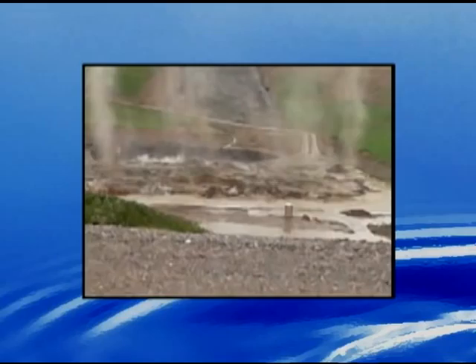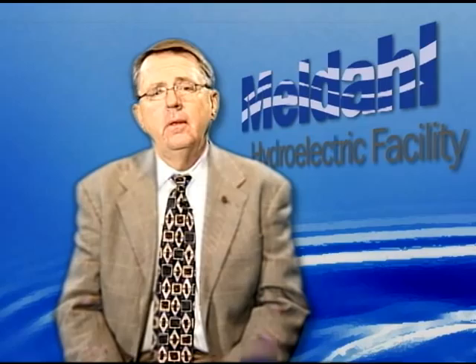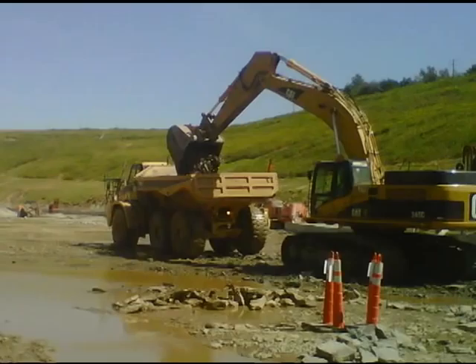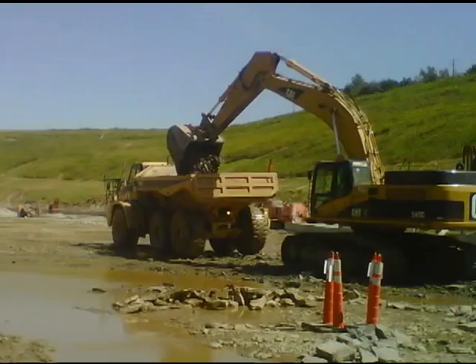The whole reason for this is that the powerhouse for our hydroelectric project sits underneath the river. The actual top of the powerhouse is submersible, so if the river rises more than three feet above the top of our powerhouse it submerges the powerhouse — and that's the way it's supposed to be. It's going to go fairly deep into the bedrock, and we will then pour the powerhouse foundation and the concrete for the powerhouse walls.